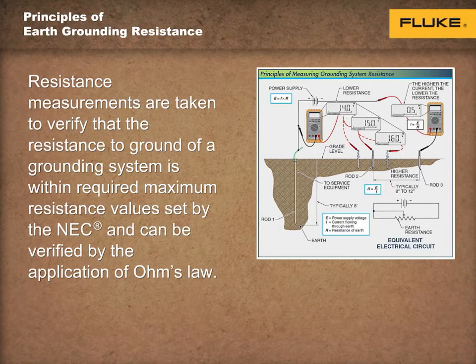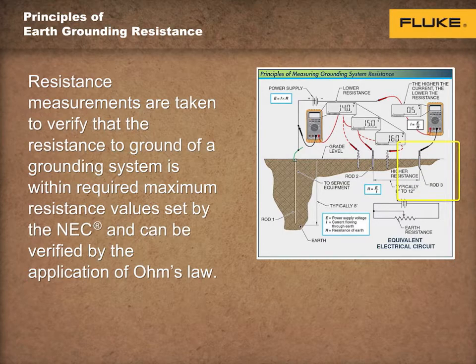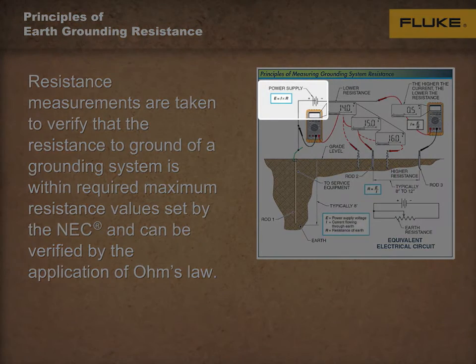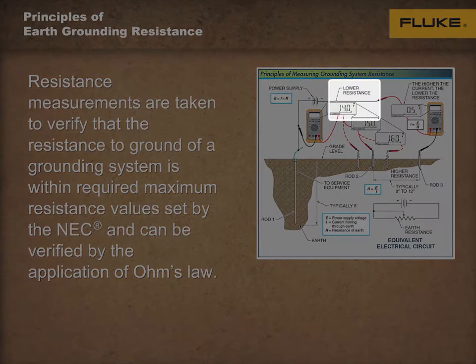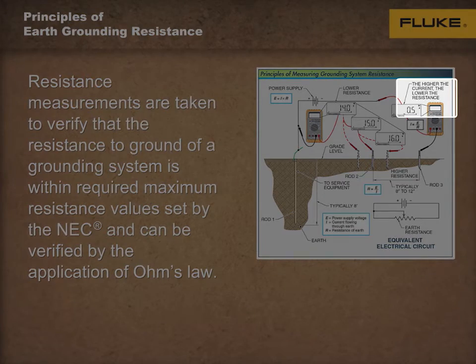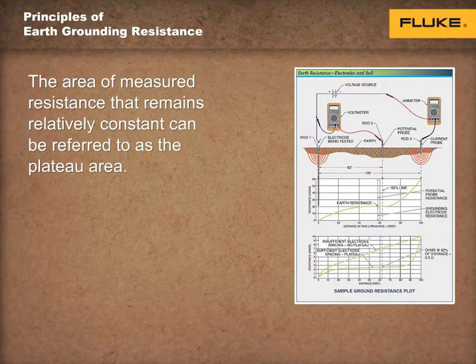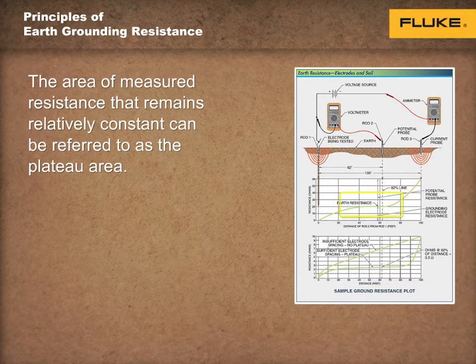Source voltage from a power supply is applied between the outside rods, rod 1 and rod 3. A current measurement device is connected into the circuit to measure the current draw from the power supply. The current draw from the power supply is inversely proportional to the resistance of the circuit created, or earth resistance. The lower the measured resistance, the higher the fault current carrying capacity of the circuit. Likewise, the higher the measured resistance, the lower the fault current carrying capacity of the circuit. For most measurements, areas are reached where the rate of increase in the resistance of the earth is low and where the resistance remains relatively constant for a set distance. The area of measurement where the resistance remains relatively constant can be referred to as a plateau area.